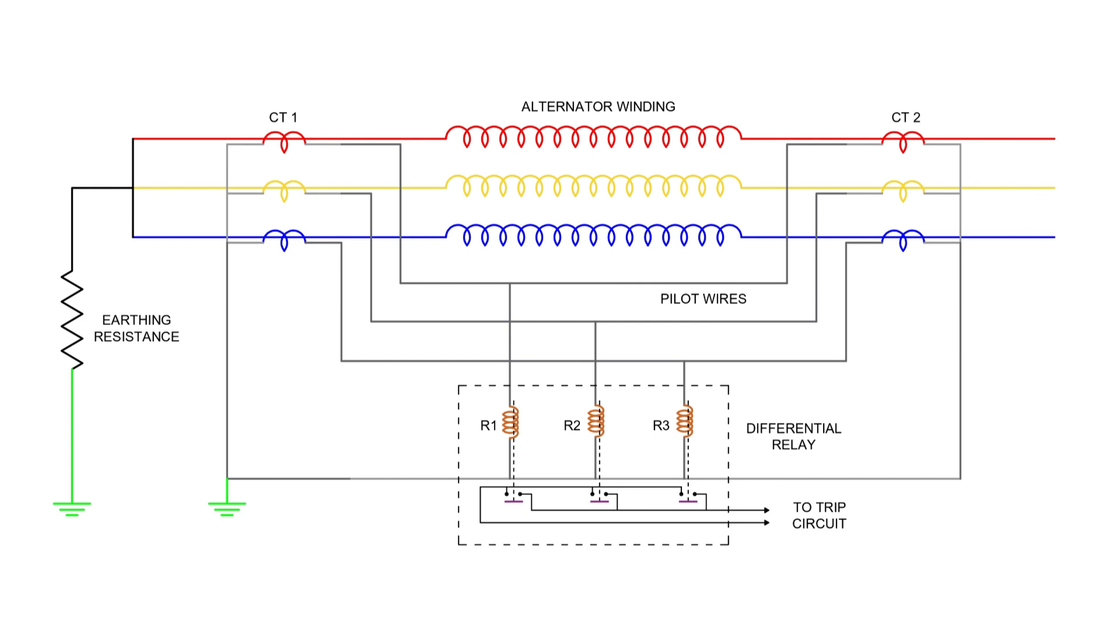Under normal operating conditions, these currents remain equal, but in the event of a fault inside the protected section, they become unequal. This difference in current is passed through a relay, which then operates to isolate the faulty section. This type of protection is also called the Merz-Price circulating current scheme.